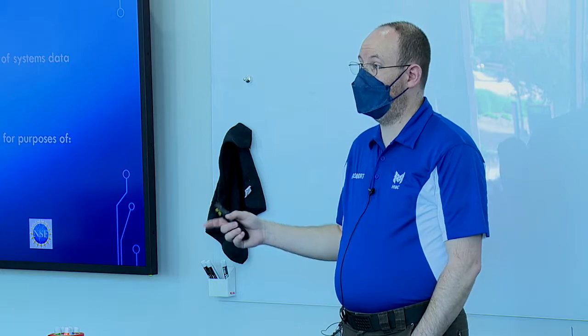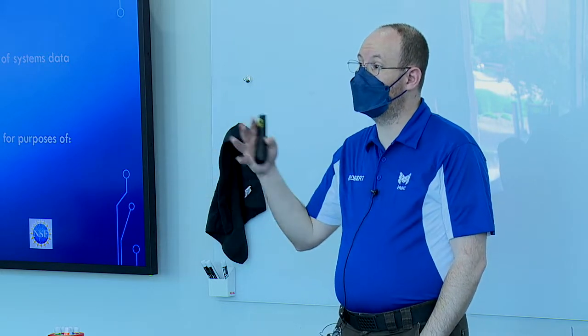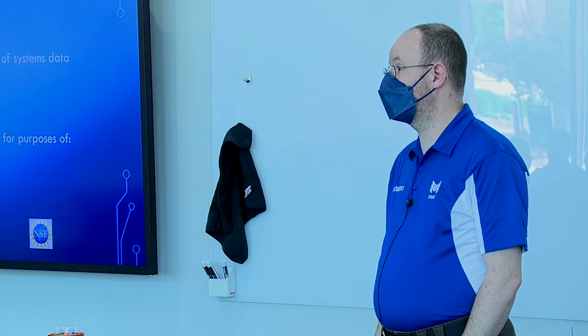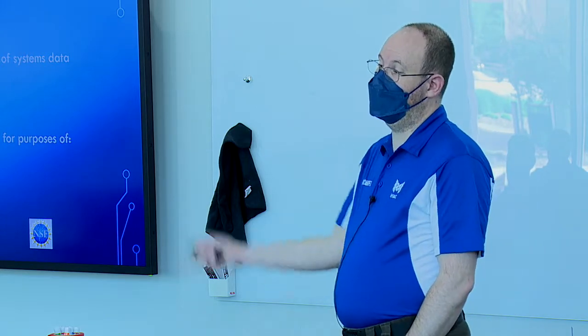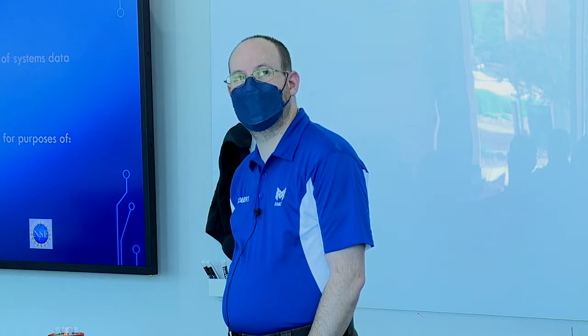But if your system doesn't have a lot of capacity, you better find a way to back up that data if you want to maintain it. And clearing space in the database could be critical too. Some older control systems, when their history log database filled up, they just stopped recording data. That was a great discovery. Hey, I got an alarm. Let me go to the history logs. Oh, it stopped logging 2 years ago. Great.